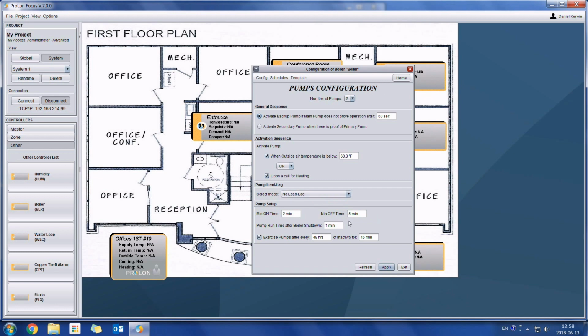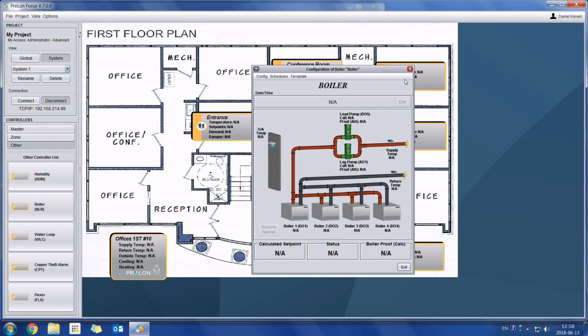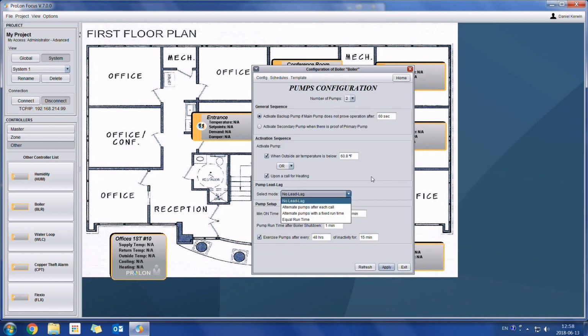If I just put the pump sequence back to the original configuration, so that we would have a lead pump and a lag pump, the pumps also have a lead lag sequence, so we can alternate pumps after each call. We can alternate pumps with a fixed runtime, which we're able to input right here, or we can use the equal runtime feature. And the pumps also have minimum on time and minimum off times.